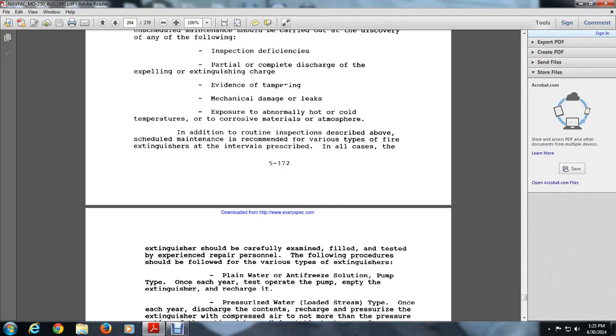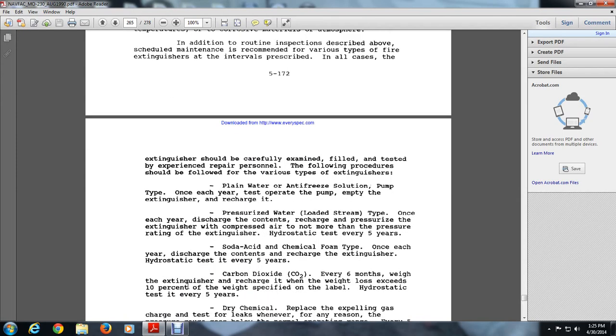Experienced repair personnel should follow procedures for the various types of extinguishers. Plain water and antifreeze solution pump type, once a year: empty the extinguisher and recharge. Pressurized water, loaded stream type, once each year: discharge the contents and recharge the pressurized extinguisher with compressed air to not more than the pressure rating. The extinguisher is hydrostatically tested every 5 years. Soda acid and chemical foam type, once each year: discharge the contents, recharge the extinguisher, and hydrostatically test every 5 years.